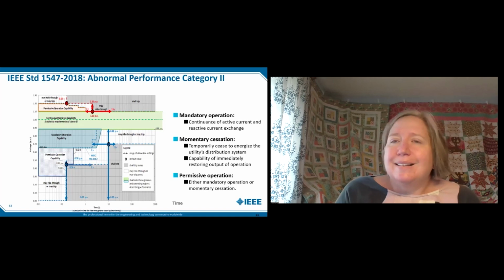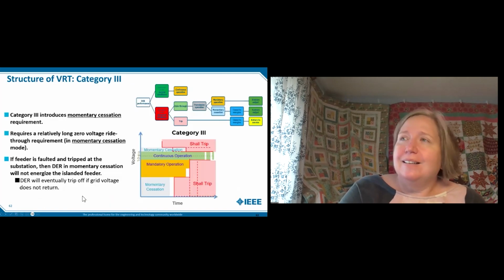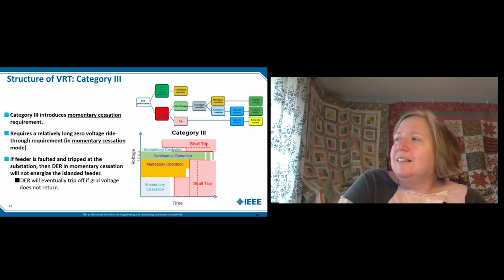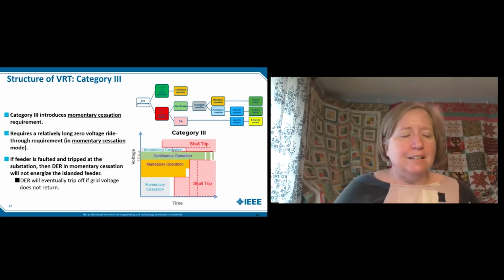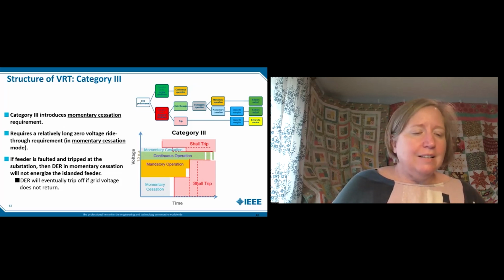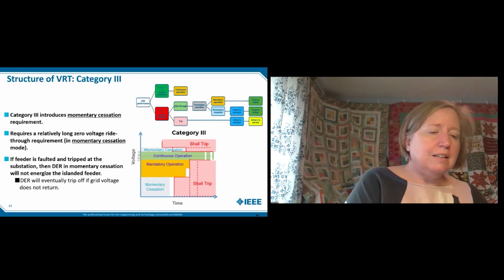Jeanette, but before we leave the mandatory operation, am I correct in my recollection that green, continuous operation, aligns with ANSI C84? I believe so, yes. And, having done a bit of engineering support in Alaska, one challenge is their continuous operating range can go outside of C84. The question is, with this future Category 4, will they be opening up some of the ranges to account for the fact that voltage and frequency on very weak islanded systems may be outside of traditional metrics like ANSI C84? I believe so, yes. Thank you.